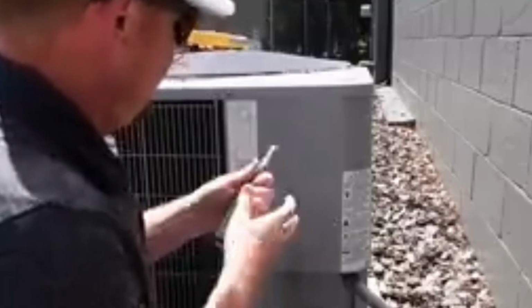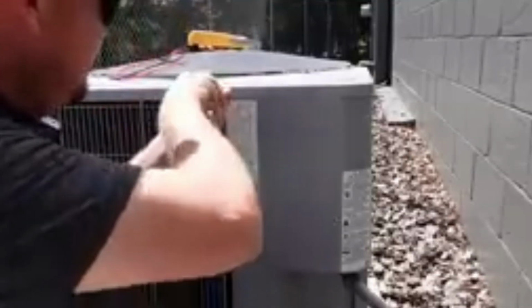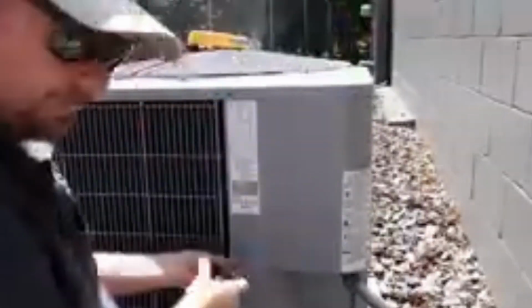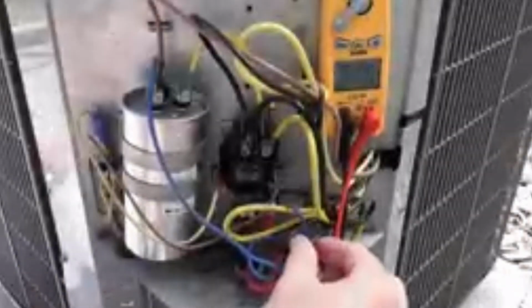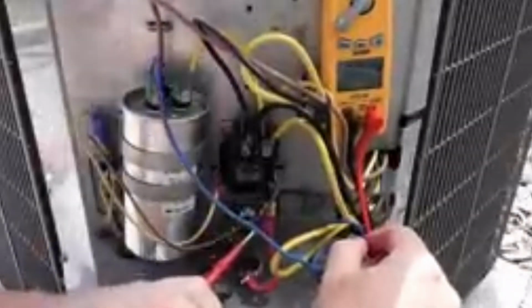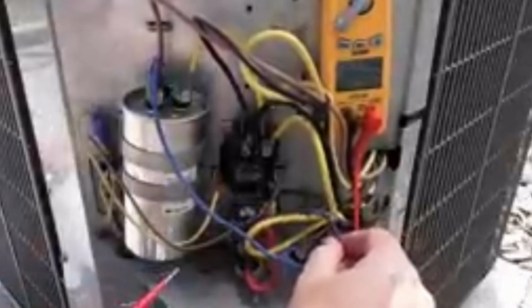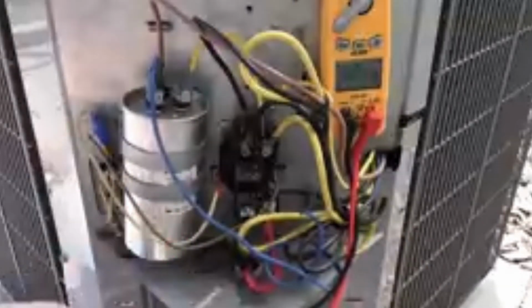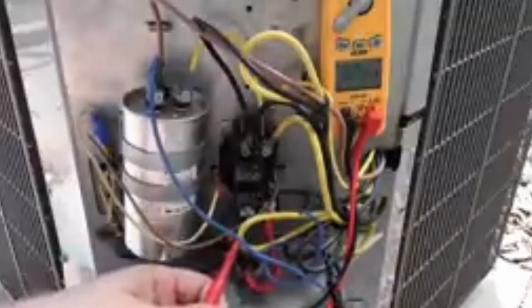With the power safely off, now I can remove the electrical panel to gain access to all of the electrical components. Now we're going to do a safety check from each of our incoming lines here. This is L1 and L2 coming in to ground to make sure that we don't measure any voltage.